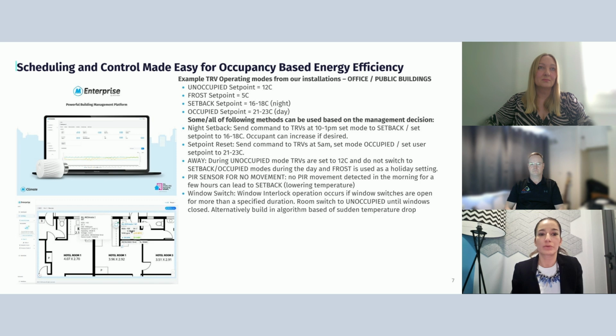Again, a lot of the scenarios work around not heating up a room if there is no movement detected there. So from the night mode of 16 degrees, you start heating up at, let's say, 5 or 6 a.m. to 18 degrees. If a room is not occupied based on a schedule, or based on the movement detected by the sensors, you don't really need to heat it to 21 or 23 degrees. And all these scenarios, depending on the use case, we're happy to advise on as well, based on customers we have around Europe. But really, that allows you to easily set up rules that save energy over the long run without having to intervene in your energy consumption every day.